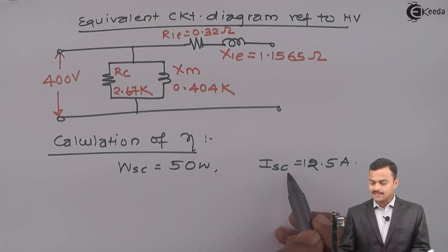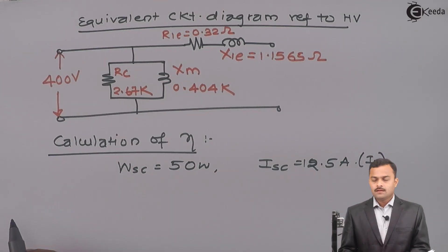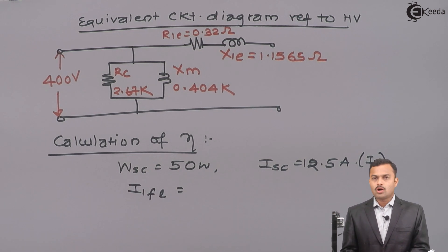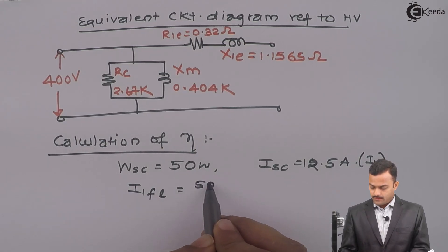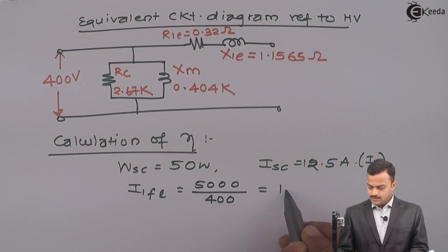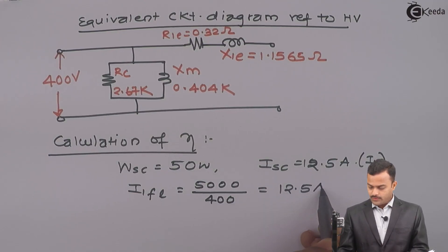So, I can say this current is I1. So, to get a full load copper loss I should know I1FL. So, how do you get I1FL? It is very simple. It is KVA 5000 divided by primary side voltage which is 400. So, if you solve you will get I1FL. So, I1FL is 12.5 ampere.